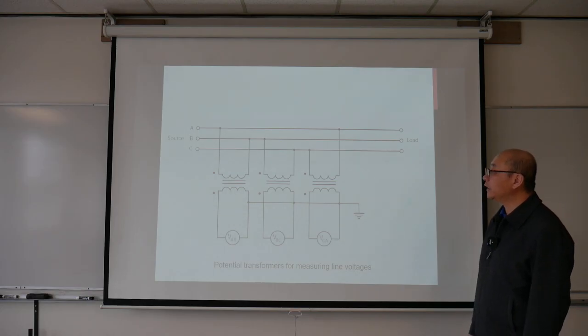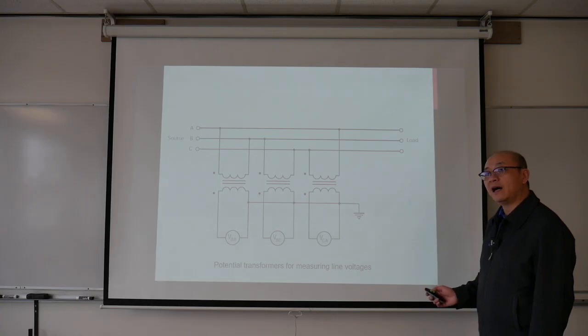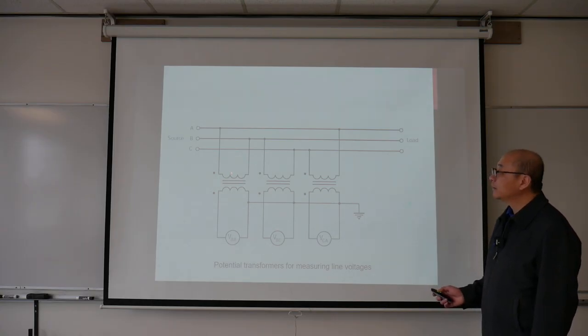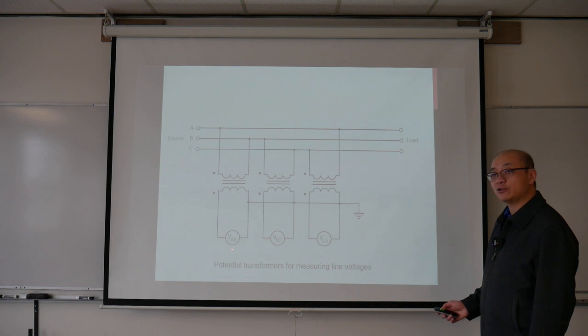This picture shows three potential transformers measuring the line voltage. You can see the primary side of those potential transformers is connected between two of the lines. So the output on the secondary side goes to an indicator showing the line voltage on the primary side.